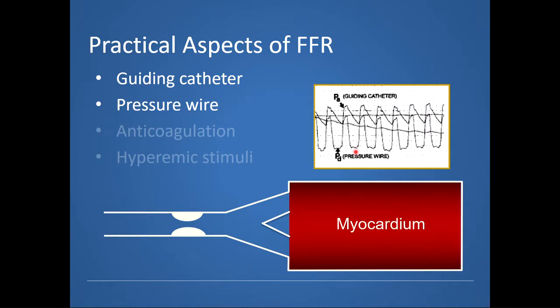Signal drift can happen due to a variety of causes — sometimes due to a temperature change in the area of the sensor. After the pressure wire assessment, we pull it back to confirm there has not been significant signal drift.